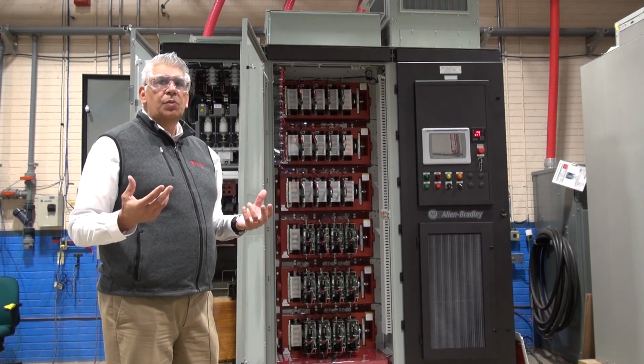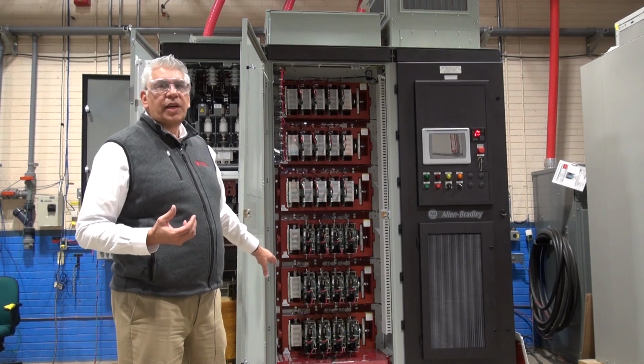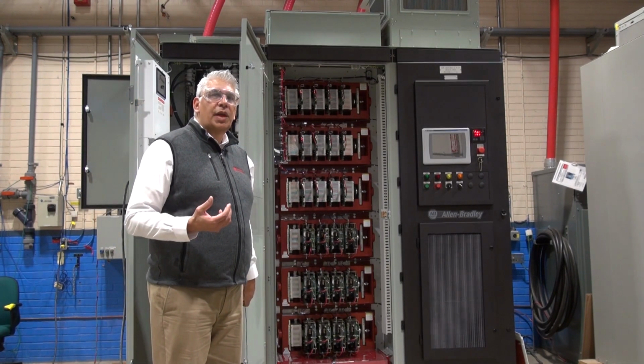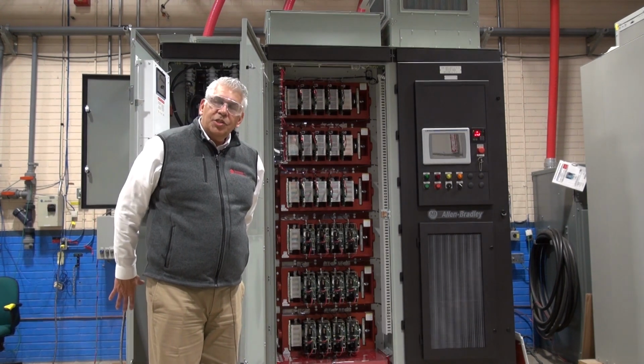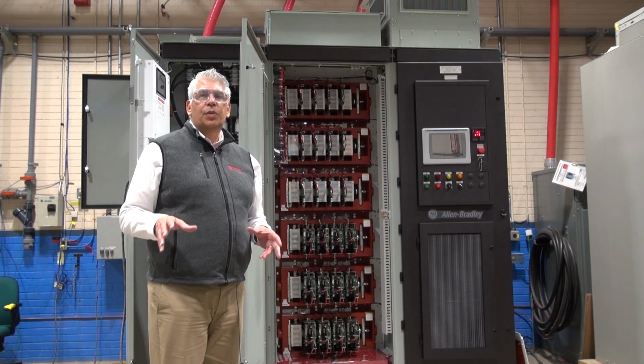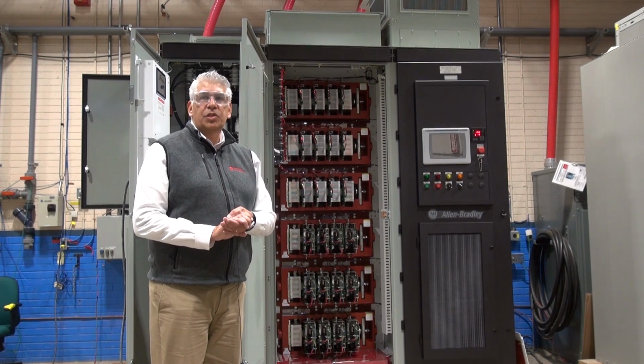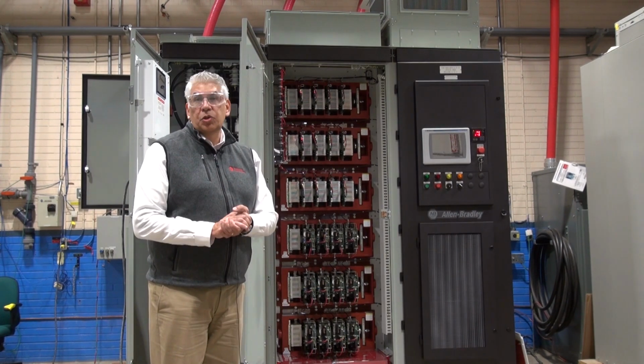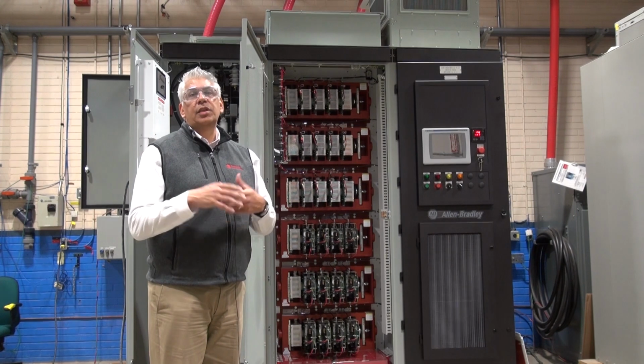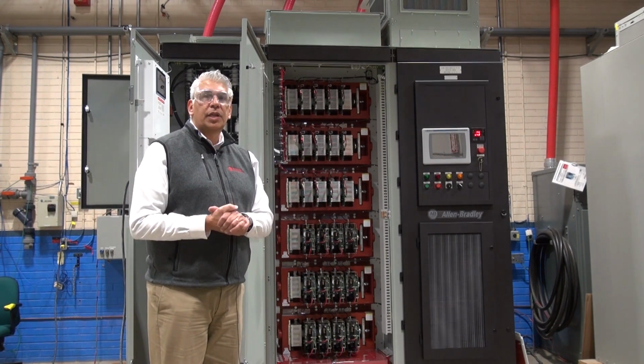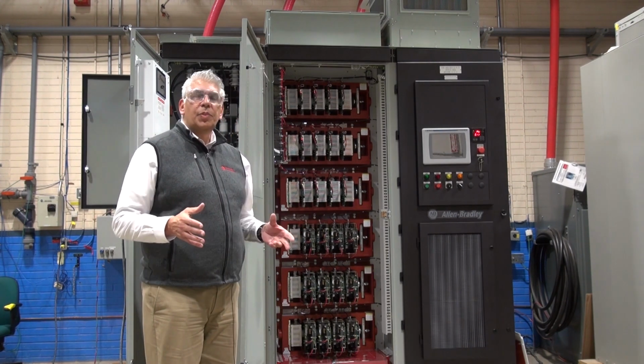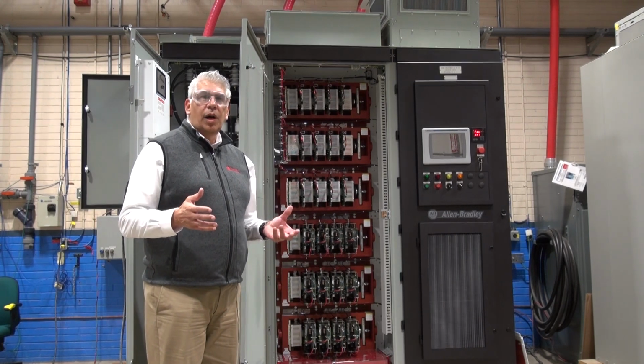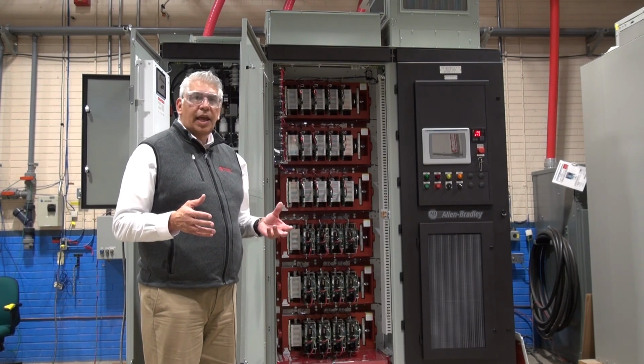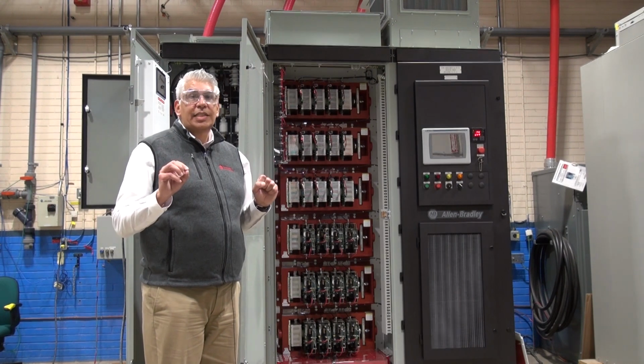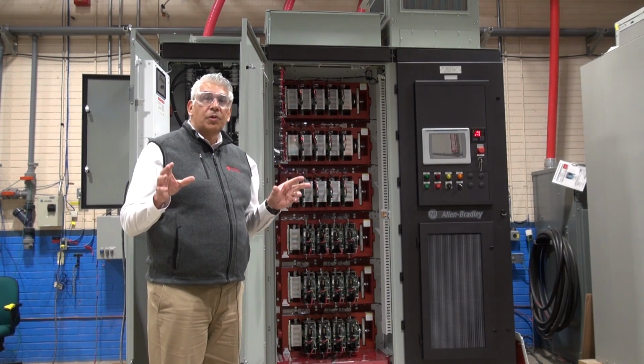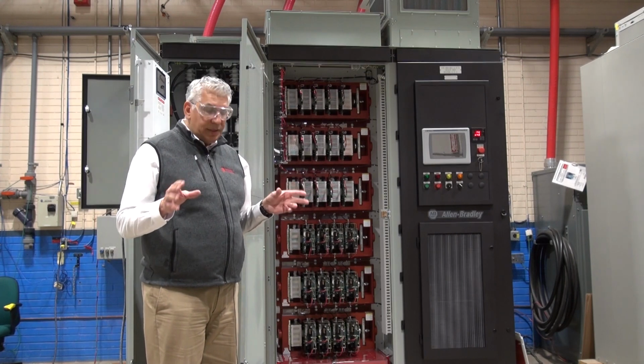Just 2 things I really wanted to focus on. It's really the devices themselves and what it gives you as a benefit. First of all, just to recap, getting rid of the transformer on the front end means a very high efficiency drive and reduces your operating costs. The higher the efficiency, the lower your operating costs. So that's the first thing I wanted to point out. And the second part is really around the topology and the fact that it has what we call an SGCT as a switching device. That refers to symmetrical gate commutated thyristor.